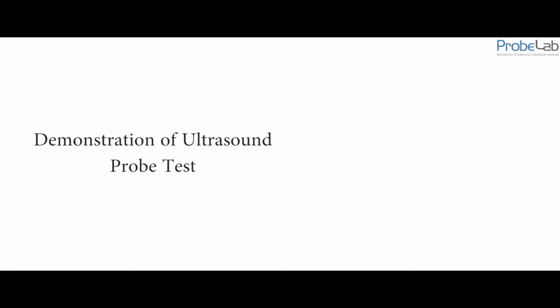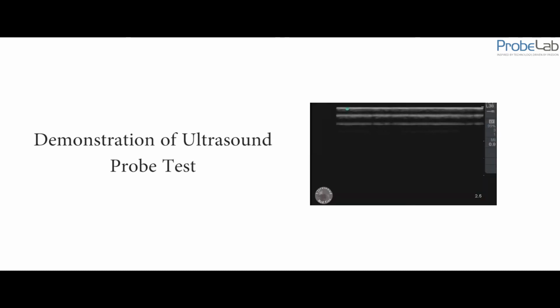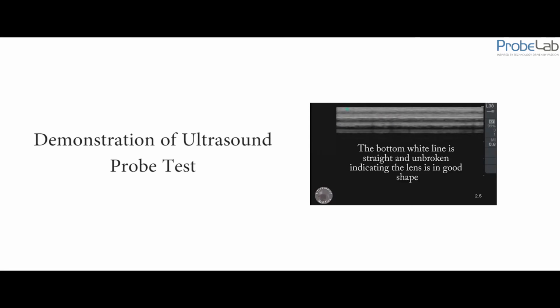So what we're going to do first is we're going to take our probe. In this case it's about a 7.5 megahertz linear array probe used for POCUS, point of care anesthesia. I'm going to go ahead and turn my gain of my machine up to see the ring down come. Now as I look at the bottom or the far field of the ring down, I'm looking for any discrepancies or unevenness. This could indicate damage to the lens.